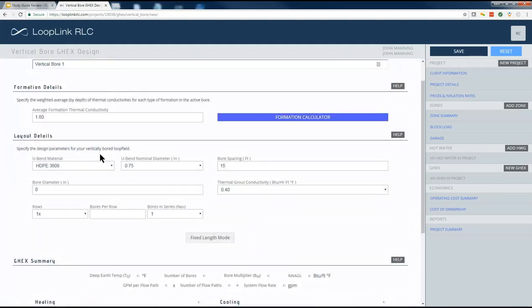Once you've got your soil properties popped in, next thing you need to specify is your loop type. We've got our two basic kinds of HDPE, which actually don't affect the calculations at all. And then there's thermally enhanced HDPE and PEX-A if you want to try to use that in the ground loop as well. I'll just leave it at the default HDPE material. And then the next thing that you need to specify is your U-bend diameter.